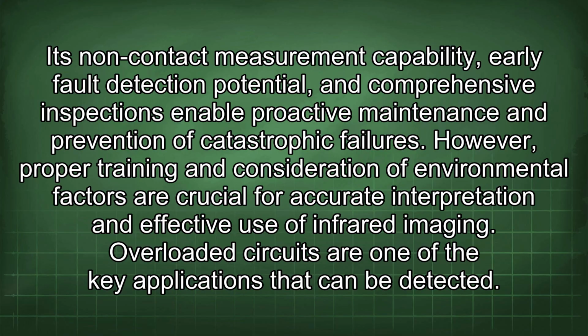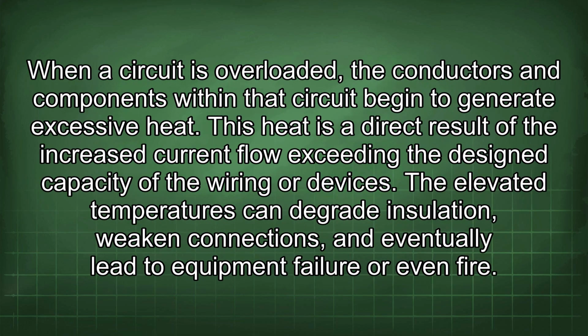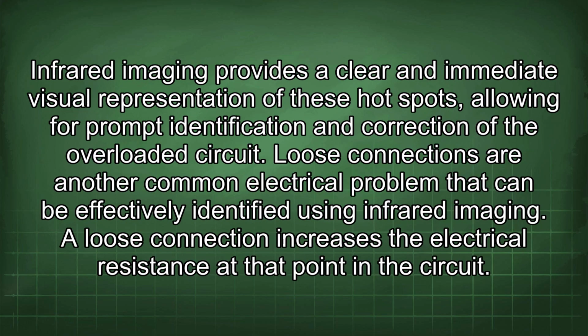Overloaded circuits are one of the key applications that can be detected. When a circuit is overloaded, the conductors and components within that circuit begin to generate excessive heat. This heat is a direct result of the increased current flow exceeding the design capacity of the wiring or devices. The elevated temperatures can degrade insulation, weaken connections, and eventually lead to equipment failure or even fire.